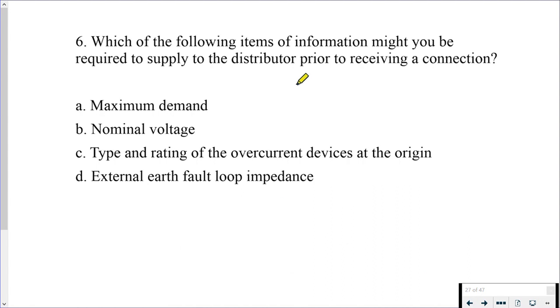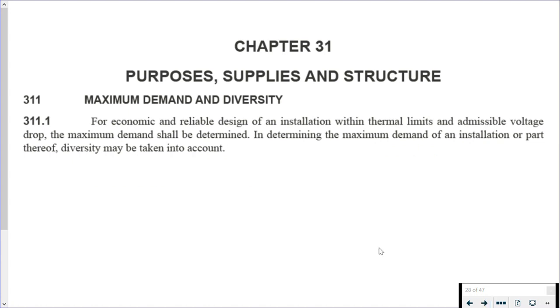Question 6: which of the following items of information might you be required to supply to the distributor prior to receiving a connection? If you have ever had to contact the DNO, the distributor, you know that upon inquiry, Regulation 28, the ESQCR regs, which you can find in Appendix 2 in BS 7671, upon inquiry the DNO, amongst other things, has to give you the nominal voltage, the type and rating of overcurrent protective devices at the origin of the supply, and the external earth fault loop impedance. The one thing that we have to give them is a maximum demand, and the designer carries out that calculation at the outset. So how would you find it? You would be looking for supplies, so purposes, supplies and structure down near the front of the book. And that first sentence there in 311.1 tells you that the maximum demand has to be determined.